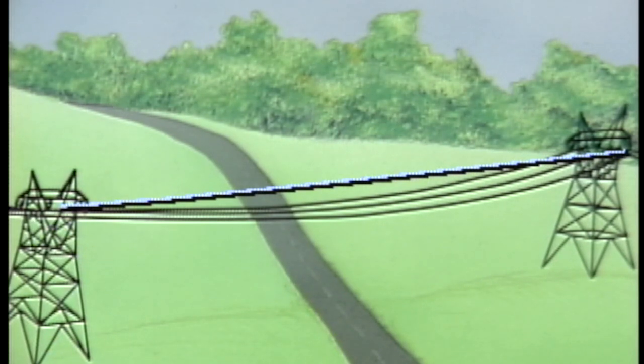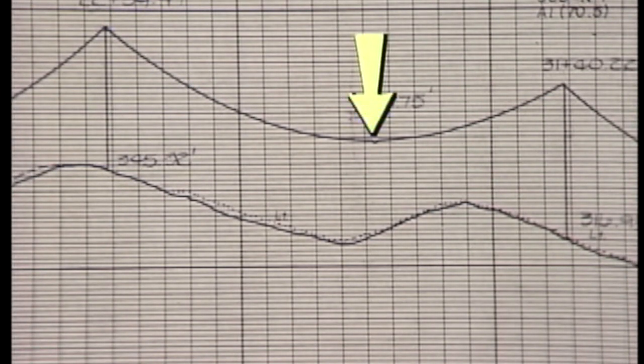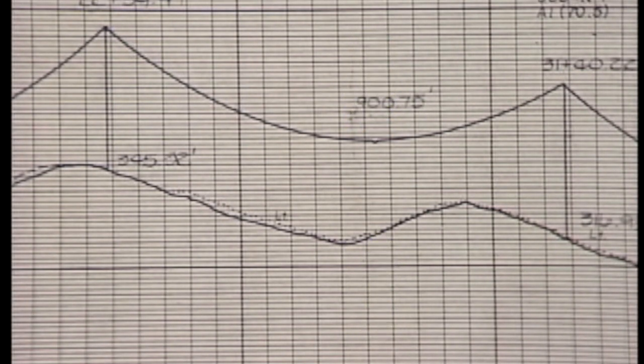The amount of tension on the wire determines the amount of sag. Proper sagging is important for many reasons. Company policies and electrical codes that cover the construction and operation of transmission lines generally require that a specific minimum distance be maintained between the lowest point of a conductor and either ground or other conductors on the structure. Proper sagging makes it possible to maintain this clearance.